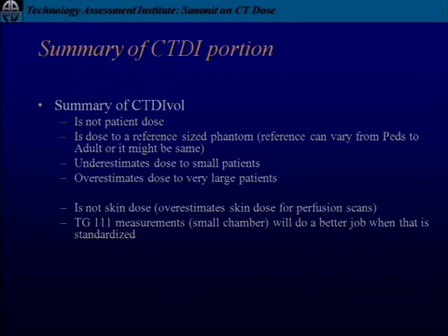It's on the website. For those of you that don't know what I'm talking about, I'll be very brief. CTDI is measured in a phantom, no table motion, with a 100 millimeter pencil chamber. Task Group 111 has a couple different protocols, but one of them is for a protocol that does not involve table motion. Again, you do not move the table, but it's done with a smaller chamber.